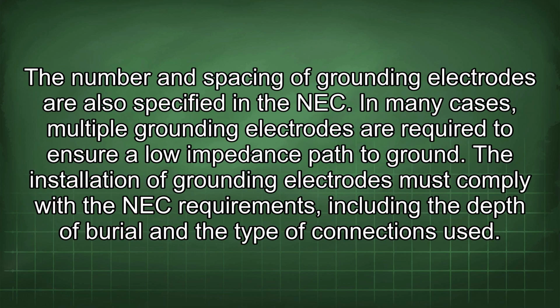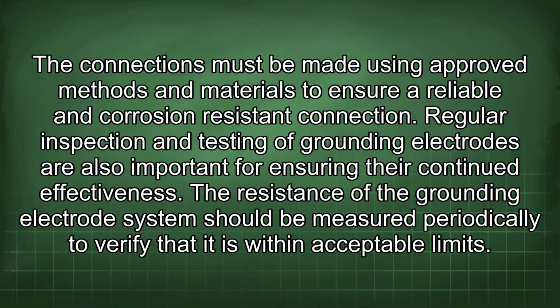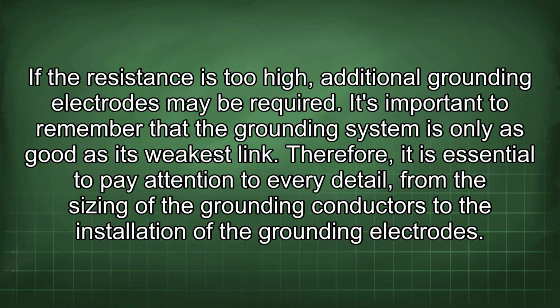The number and spacing of grounding electrodes are also specified in the NEC. In many cases, multiple grounding electrodes are required to ensure a low impedance path to ground. The installation of grounding electrodes must comply with the NEC requirements, including the depth of burial and the type of connections used. The connections must be made using approved methods and materials to ensure a reliable and corrosion-resistant connection. Regular inspection and testing of grounding electrodes are also important for ensuring their continued effectiveness. The resistance of the grounding electrode system should be measured periodically to verify that it is within acceptable limits. If the resistance is too high, additional grounding electrodes may be required.